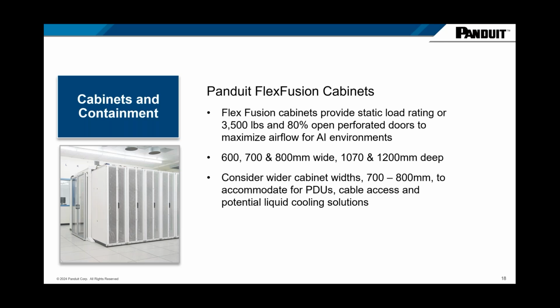We have a full offering in width and depth. I think probably considering 700 to 800 millimeter wide to accommodate extra space required in the back for access to cabling, power cables, cooling, PDUs, and whatever type of cooling you might bolt onto that. You might even be looking for deeper cabinets beyond 1200 millimeters. The consideration here is to start thinking not just about the cabinet, but what might I be bolting onto it, what might I need to access in the back, and what my cooling solution might look like.